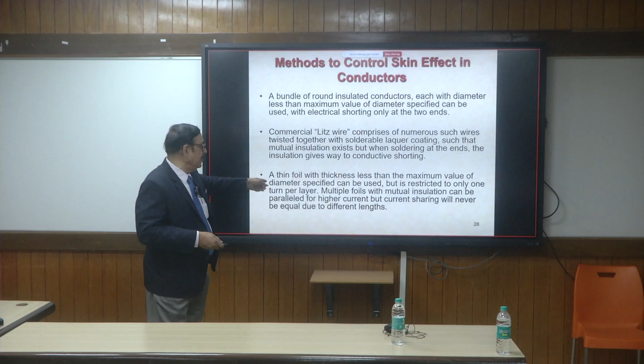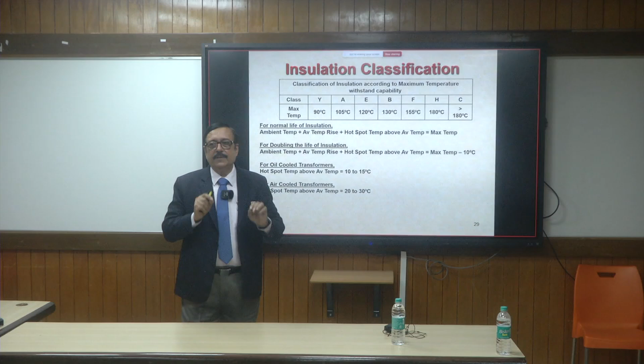Look at the insulation. After you make the winding, you have to put sufficient insulation on the winding. You might say that the wire is insulated. Yes, I agree. But when you are making a winding, there can be several cracks developed in the insulation. How do you know? As an example, put the wire into a bucket of water, pass electricity from one side and see whether the water is getting electrolyzed or not. You can make out if there are bubbles coming out. So there may be cracks. We don't do that, but just to be on the safe side, we put additional insulation on the wires to be sure that even if there are multiple cracks, we have it covered.